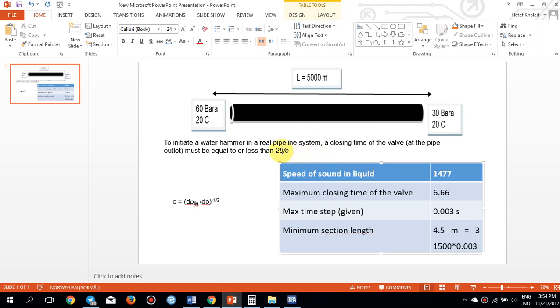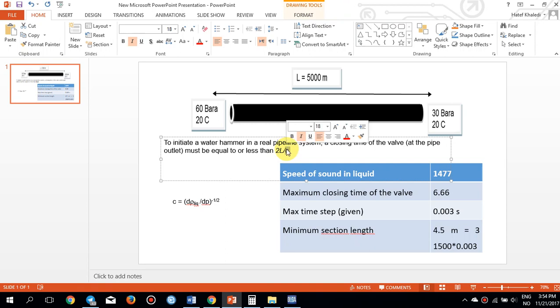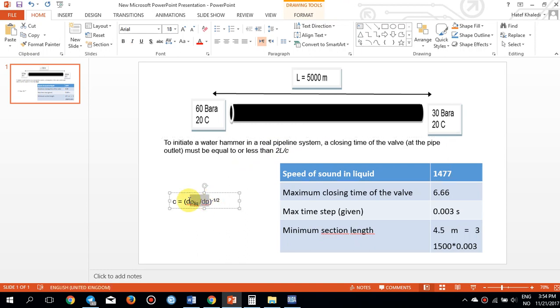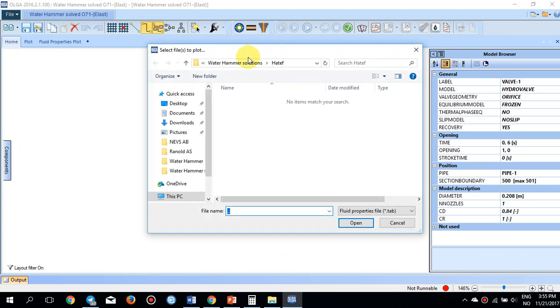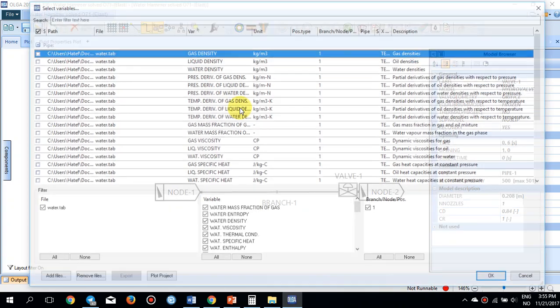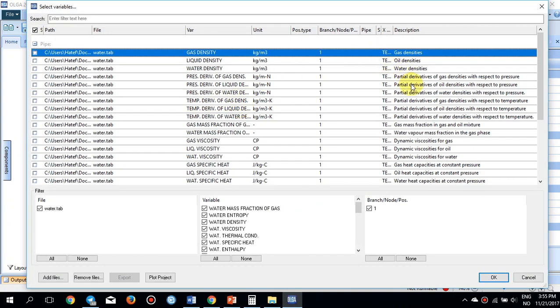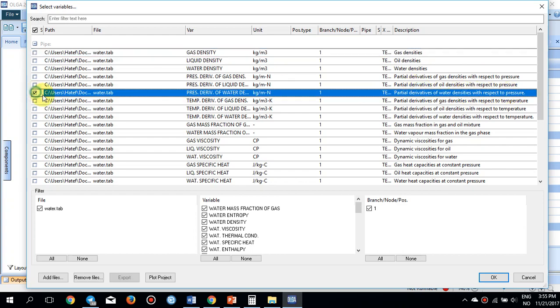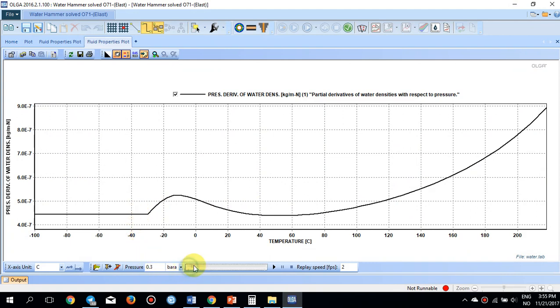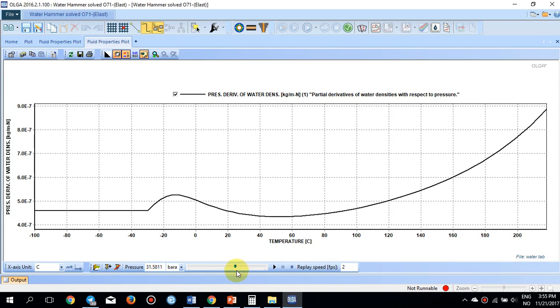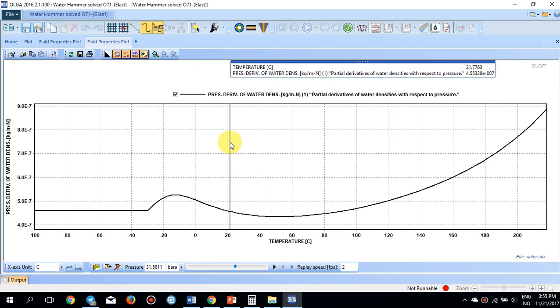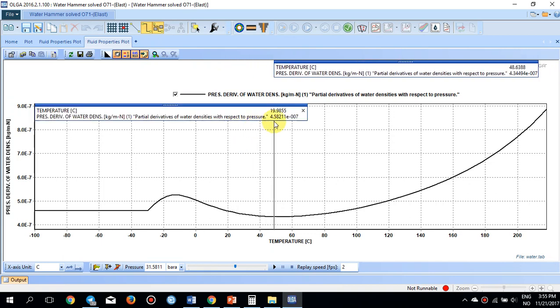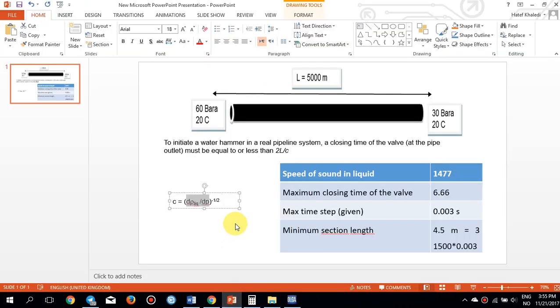C is the speed of sound in the liquid, calculated as the square root of the inverse of the partial derivative of density with respect to pressure. This derivative can be found in Olga's fluid properties tab under the water properties. Select the partial derivative of water density with respect to pressure at 30 bar and 20 degrees centigrade — the value is approximately 4.58e-7.